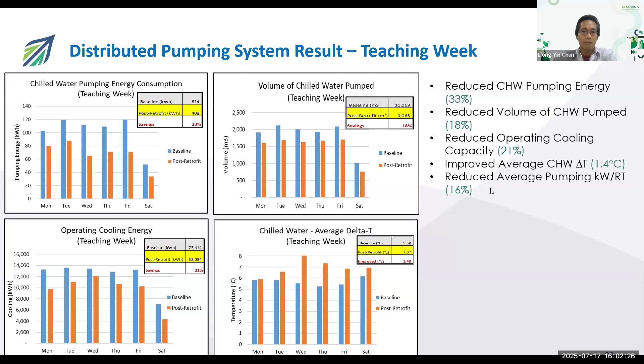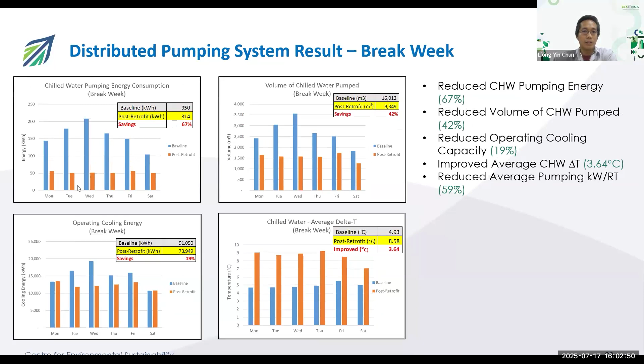And finally, for the break week, which is a low load condition, that's where we see a much bigger saving. You can see a reduction of the pumping energy of 67%, and a reduction of the average pumping kilowatt per ton of up to 59% in this case. So it's a great reduction in the energy.